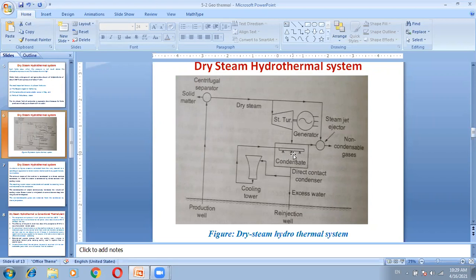These condensers are of direct contact type. Cooling water coming from the cooling tower mixes with the low pressure, low temperature steam entering through the turbine, so it is converted into condensate, cooled again, and supplied back to the cooling tower. Since steam is in direct contact with cooling water, there may be excess water available in this condenser, and this excess water is re-injected into the underground earth.